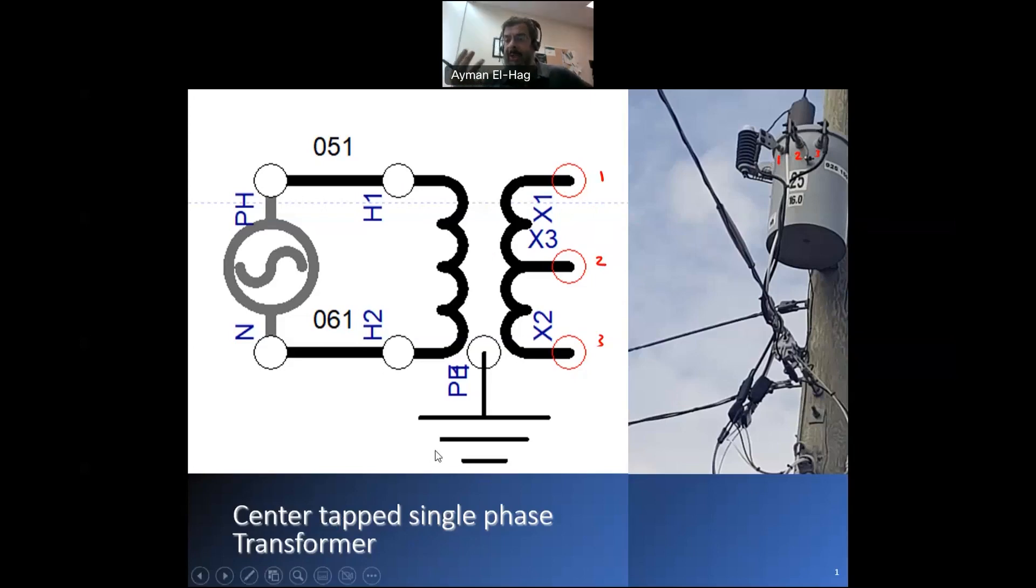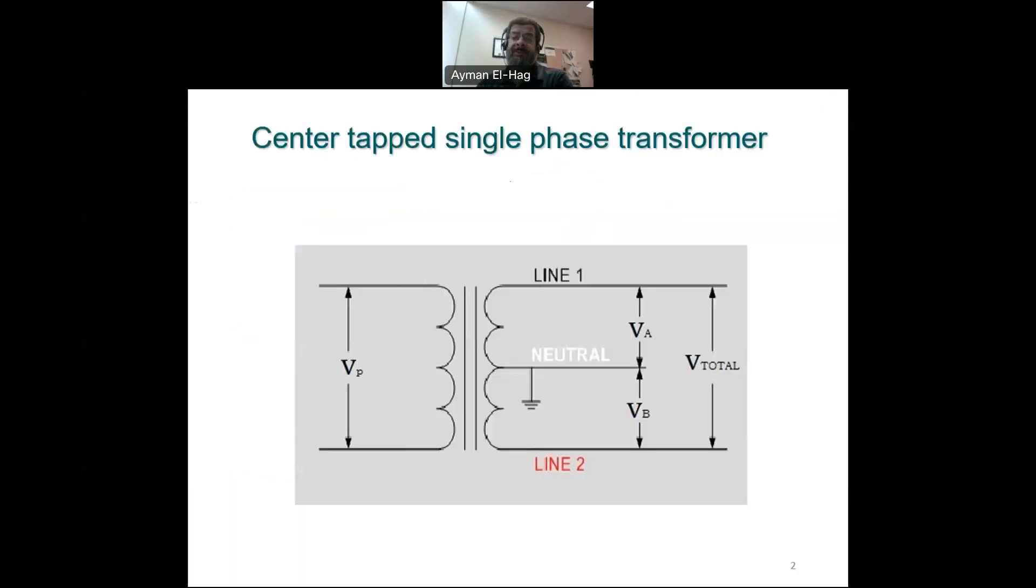So let's have a look at why we need this type of transformer and why we have these three bushings. Basically, the center tapped transformers, from its name, at the center of the secondary side you will have one wire. So the number of turns from point one to point two is exactly equal to the number of turns between point two and point three, meaning that the voltage between line one and the center tap is equal to the voltage between line two and the center tap.